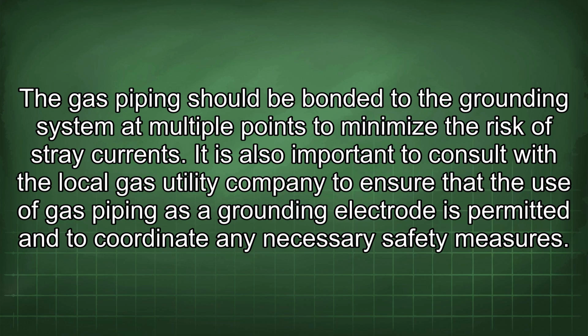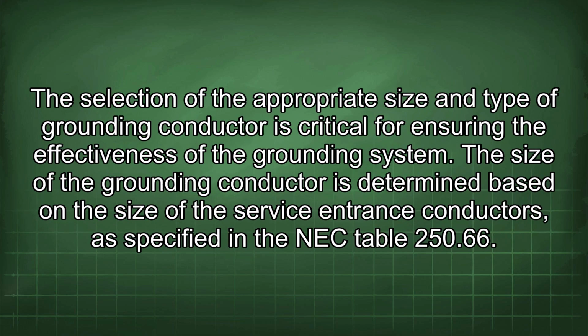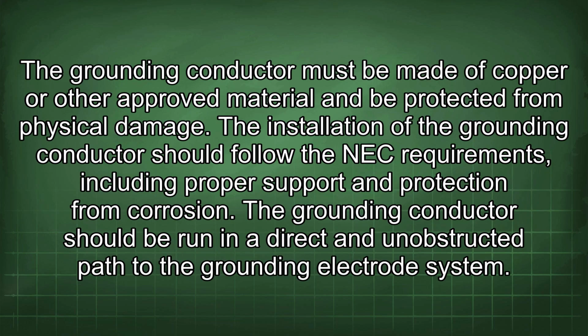It is also important to consult with the local gas utility company to ensure that the use of gas piping as a grounding electrode is permitted and to coordinate any necessary safety measures. The selection of the appropriate size and type of grounding conductor is critical for ensuring the effectiveness of the grounding system. The size of the grounding conductor is determined based on the size of the service entrance conductors, as specified in the NEC Table 250.66. The grounding conductor must be made of copper or other approved material and be protected from physical damage.